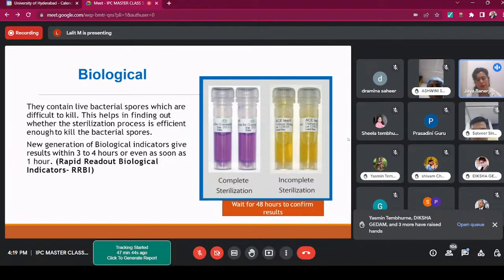Geobacillus stearothermophilus is used for the steam and for the plasma sterilizer, whereas for ethylene oxide, that is ETO, we use Bacillus atrophaeus. Next, please.